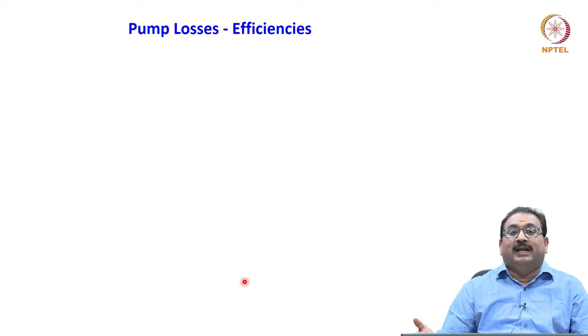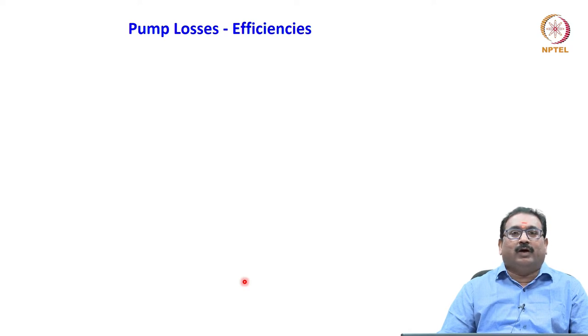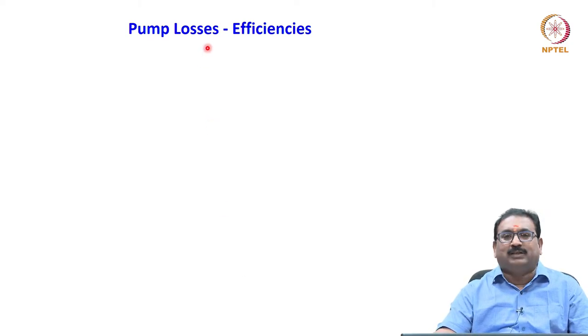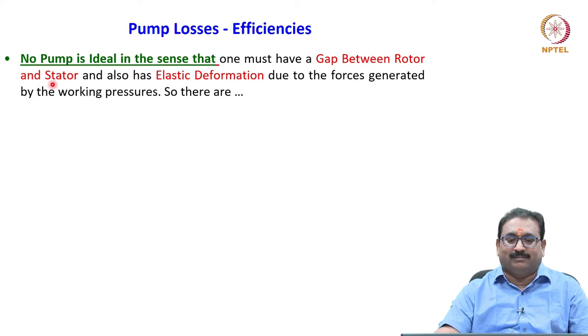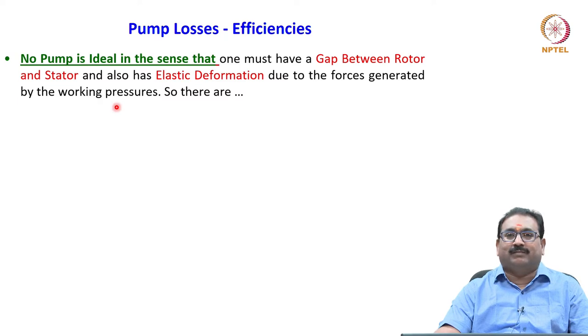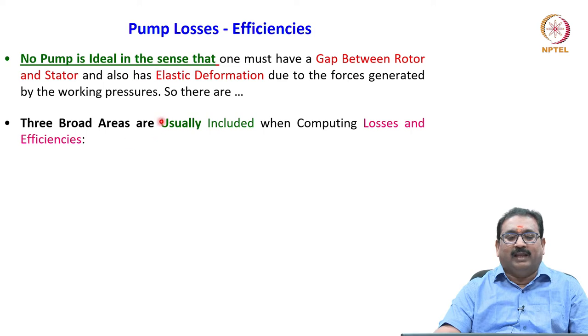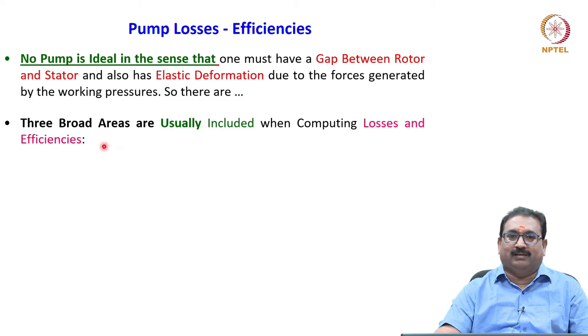This is what you can call the ideal pump. But as I said, there are no ideal pumps in existence — there is always a loss. To understand this, we must know what the pump losses are, that is, efficiency. No pump is ideal in the sense that there must be a gap between the rotor and the stator, and also elastic deformation due to forces from working pressures. There are three broad areas usually included when computing losses and efficiencies.